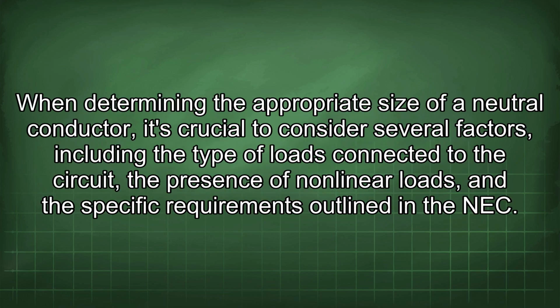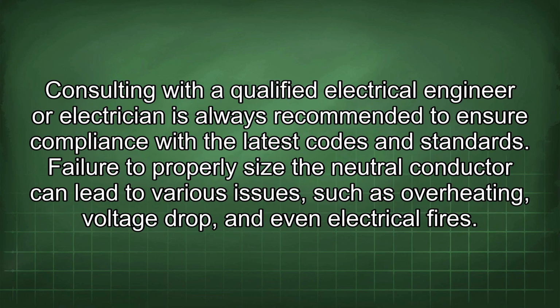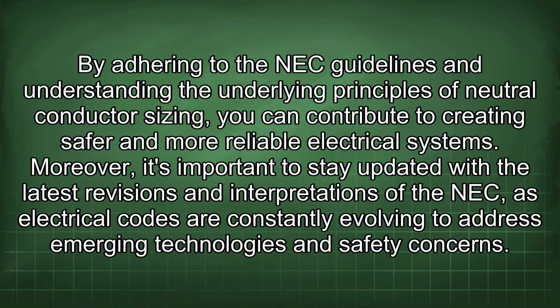When determining the appropriate size of a neutral conductor, it's crucial to consider several factors, including the type of loads connected to the circuit, the presence of nonlinear loads, and the specific requirements outlined in the NEC. Consulting with a qualified electrical engineer or electrician is always recommended to ensure compliance with the latest codes and standards. Failure to properly size the neutral conductor can lead to various issues, such as overheating, voltage drop, and even electrical fires. By adhering to the NEC guidelines and understanding the underlying principles of neutral conductor sizing, you can contribute to creating safer and more reliable electrical systems.